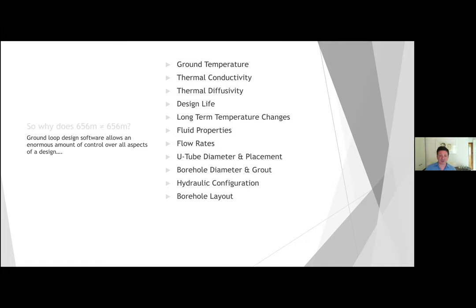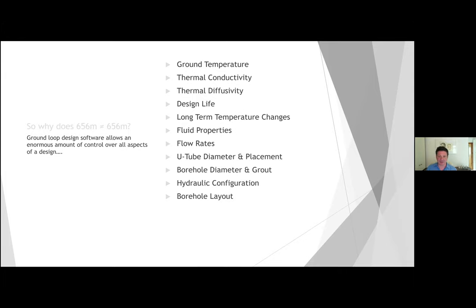We also have control over design life. The MCS requirement is for 20 years, but for many commercial buildings we put that up to 100 years because that's what the customer wants. We can also adjust the temperature changes we allow — the MCS minimum requirement for returning water temperature from the ground is zero degrees, which is a pretty arbitrary number set to give a baseline. For schemes where MCS doesn't apply, we can legitimately drop the ground loop temperature down to minus four or minus five and still maintain a sustainable system. Equally, for heating and cooling systems we can manage that ground loop temperature upward to improve both heating and cooling efficiency.